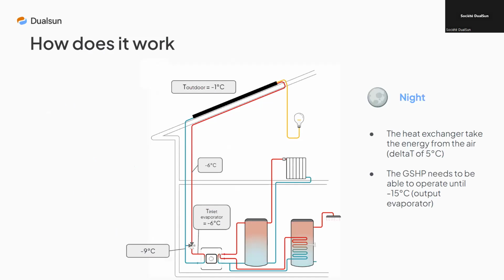Secondly, at night, it's the same mechanism, but this time we recover the heat from the air using the fins on the back that will be captured. For example, if I have a solar return here at -9 degrees in brine with an outside temperature of -1 degree, this will allow me to supply a quantity of energy and go up to -6 degrees, as we can see here, and then re-enter the heat pump.